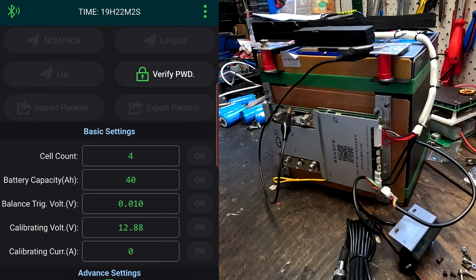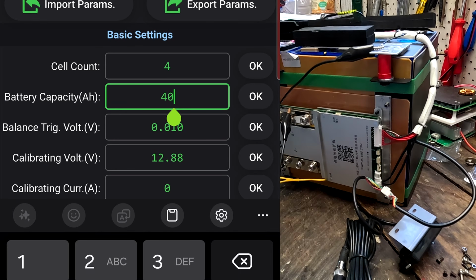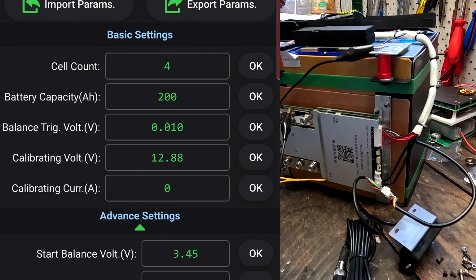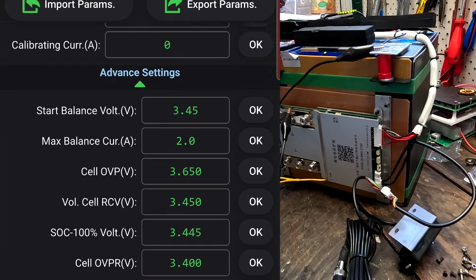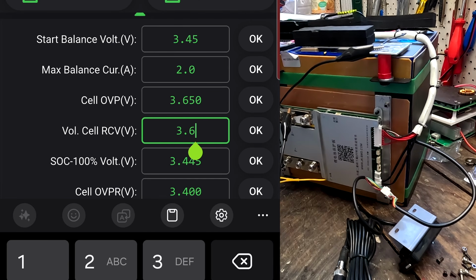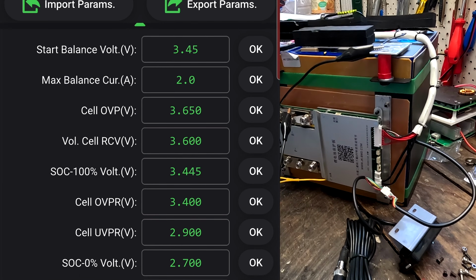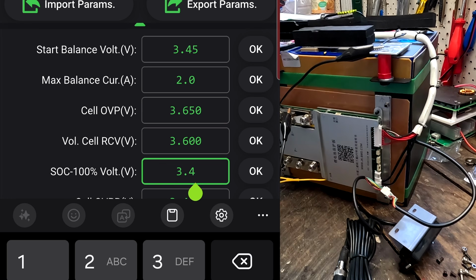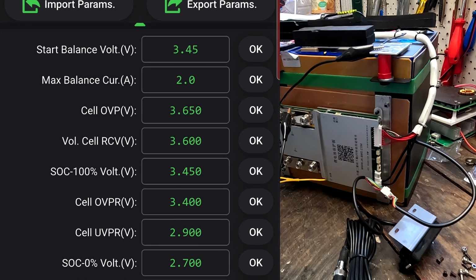Okay, we need to change some settings. So we have a capacity here of 200 ampere hours. BMS needs calibration. Yeah, I know. Balancing down to 10 millivolt delta is fine. Start balancing at 3.45 with 2 amps. 3.65. RCV, I can set this one here to 3.6 volts, because we're not using any communication with this BMS to something. And we can set this one here to 3.45 volts.